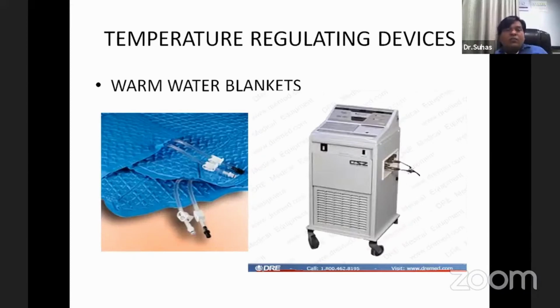So this is one device. There are many types of temperature regulating devices. In older days, we just used pre-warmed blankets to wrap the patient, but that is outdated now because those pre-warmed blankets are not effective, and because evaporation is not there, there is a risk of hypothermia also. Now, warm water blankets are considered ideal for pediatric age groups. What are warm water blankets? These are the bags, and these are the tubings for water. The tubings are connected over here. This machine maintains the constant temperature of water which we set, and that water circulates through the pores of this bag, and when the patient is placed on this water blanket, the temperature is maintained.